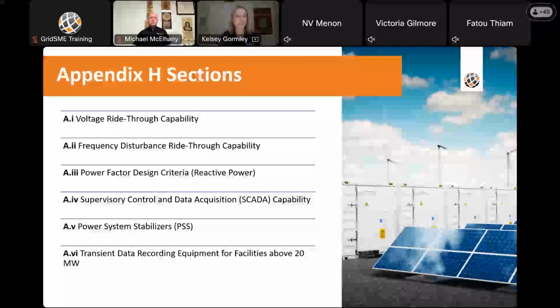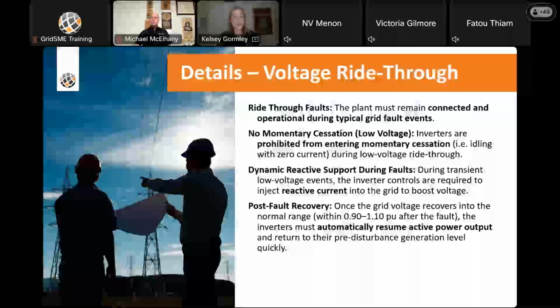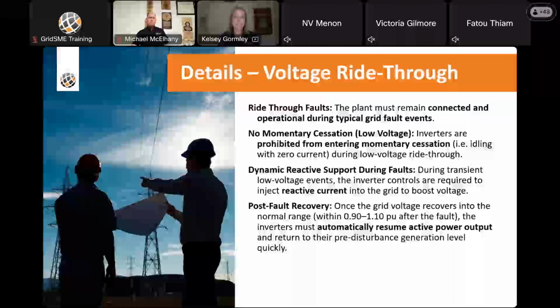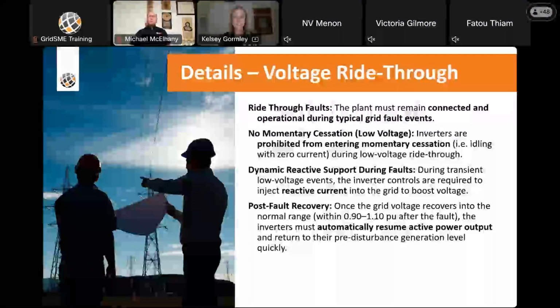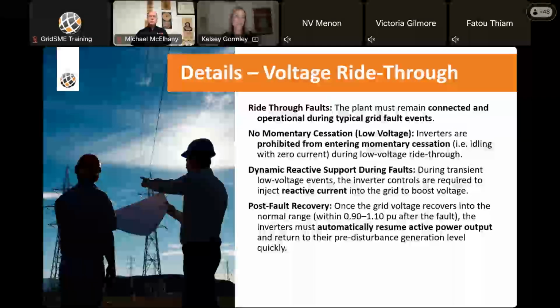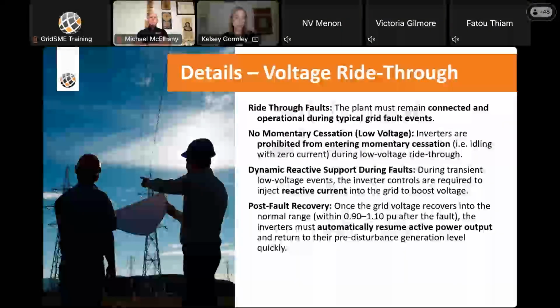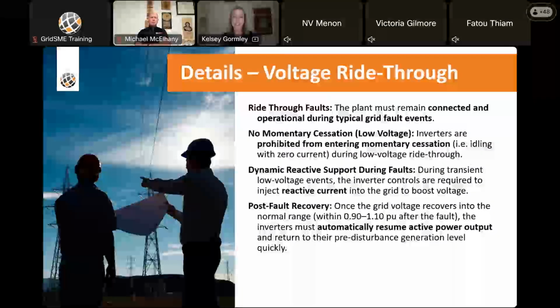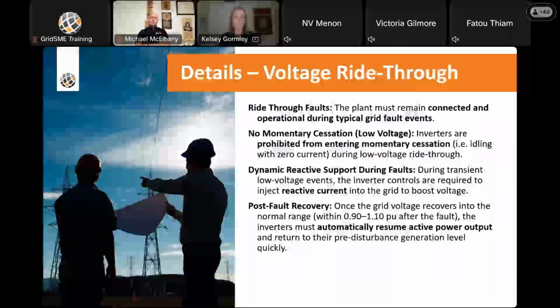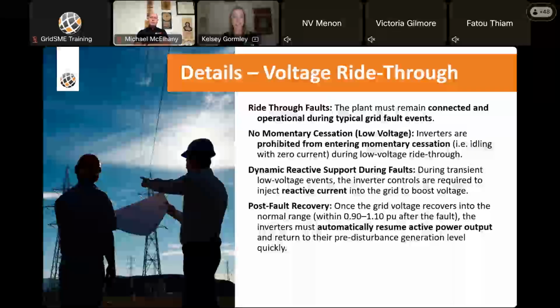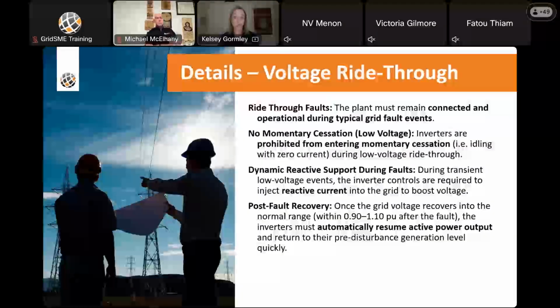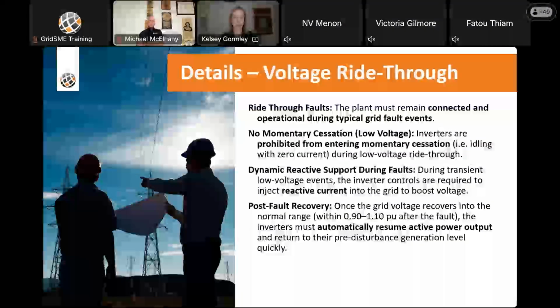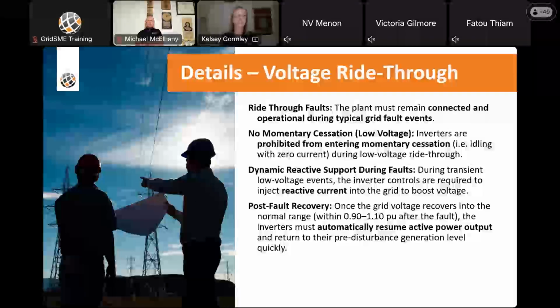So the first is voltage ride-through capability. For a normally cleared 3-phase fault at the point of interconnection lasting roughly between 4 to 9 cycles, where the POI voltage drops to near zero, the asynchronous generating facility must stay online throughout the fault as well as the subsequent recovery. Similarly, for a single-phase fault with delayed clearing, such as a backup protection clearing of a breaker failure, the facility must also ride through the low voltage period until the fault is cleared, even if that fault persists longer than a normal clearance.